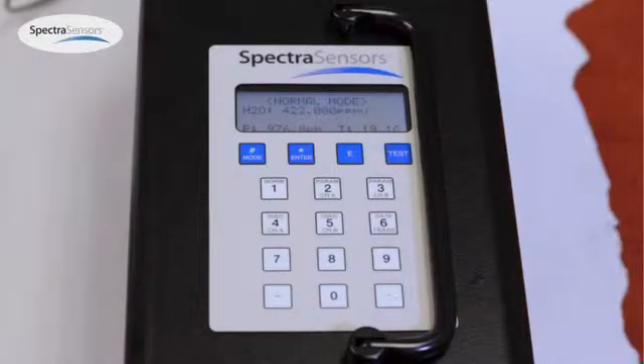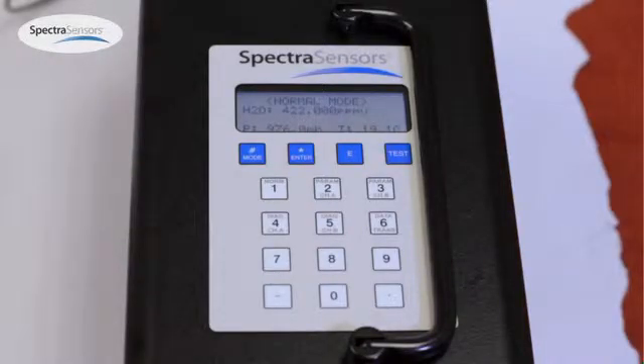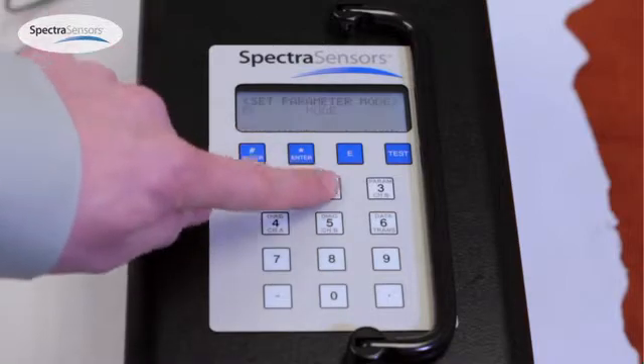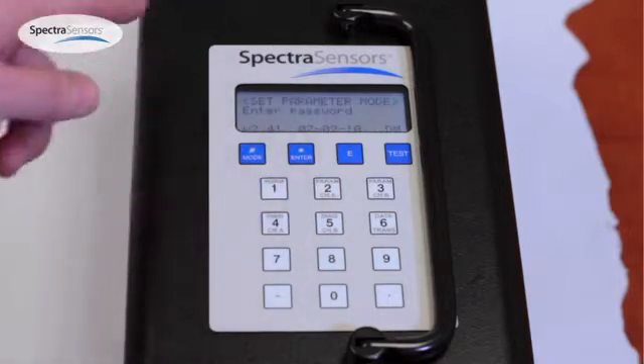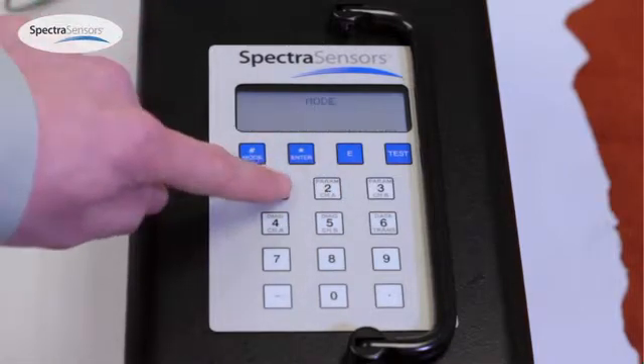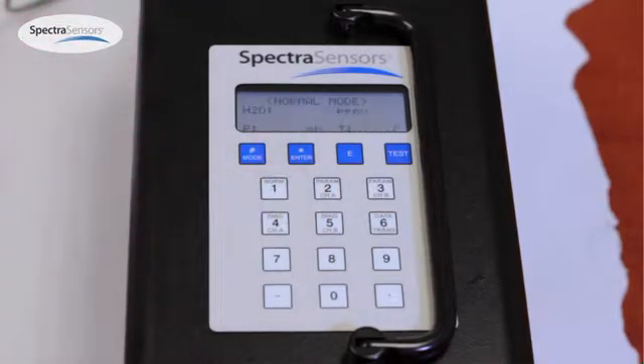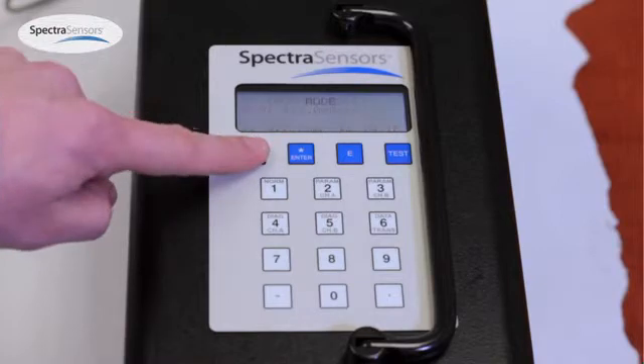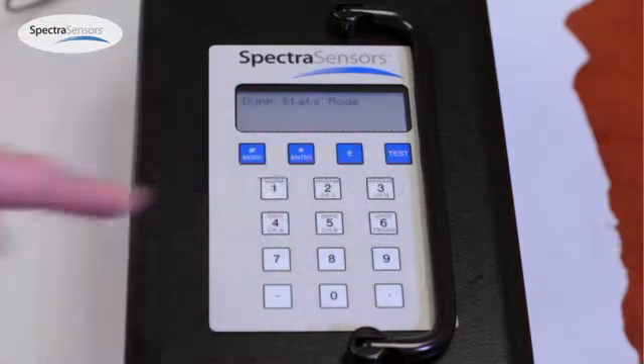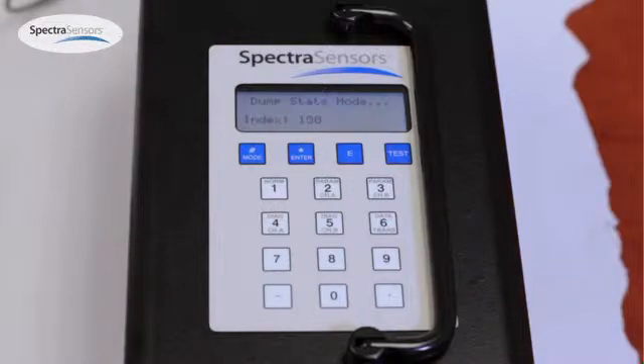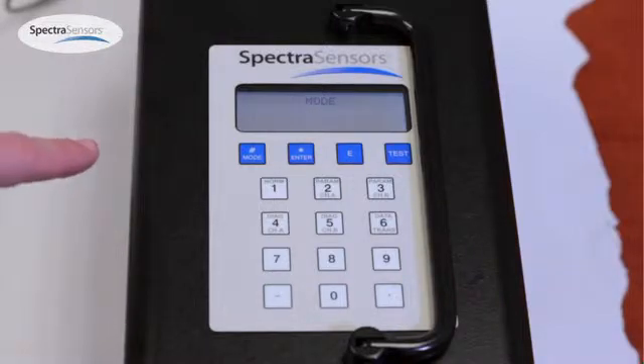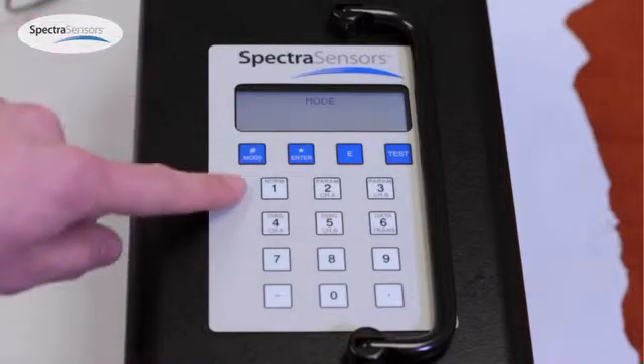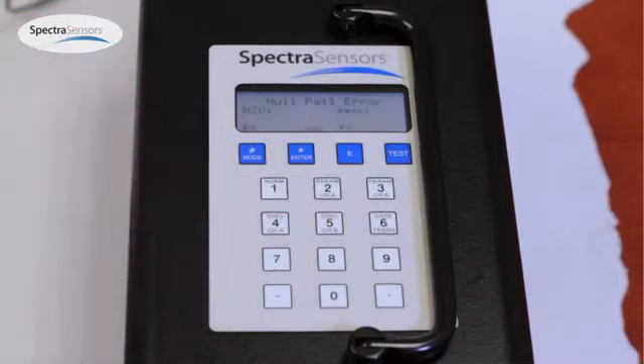By default the analyzer is outputting in normal mode. If you're in another menu, say the parameter mode, then you'll need to press pound and one to return to the normal mode and get normal output. When you're ready for your data download, press the pound button and six to download the spectrum information to your computer. This will take a minute and when it's done the analyzer will display mode and then press pound and one.